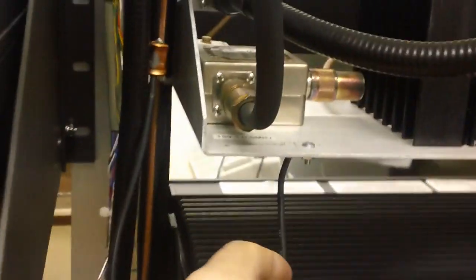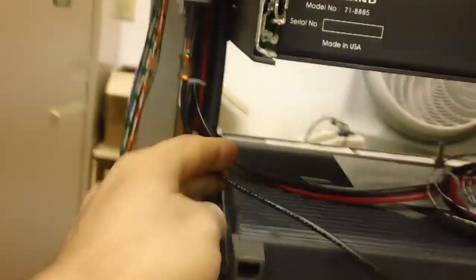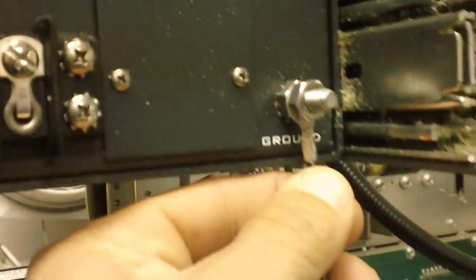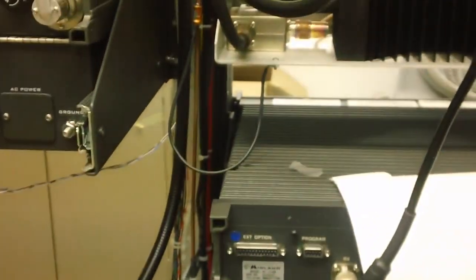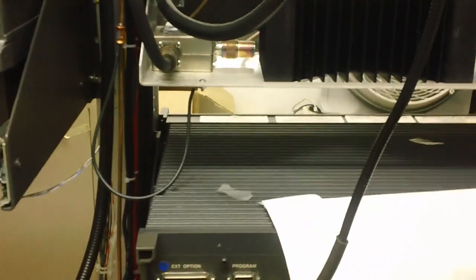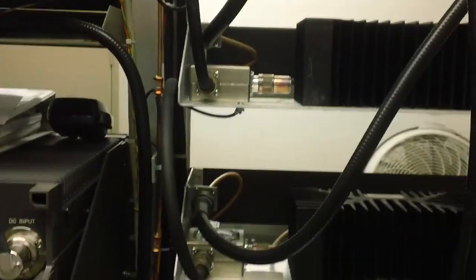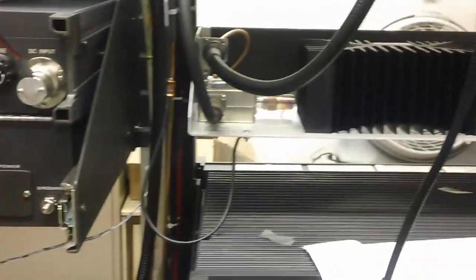I have another one grounding out to this tray, and a third radio grounding out to this tray as well. For the radios themselves, everything is grounded to earth ground — one, two, three. All this equipment, the case itself, is bonded to earth ground. That's just an example of the actual equipment.